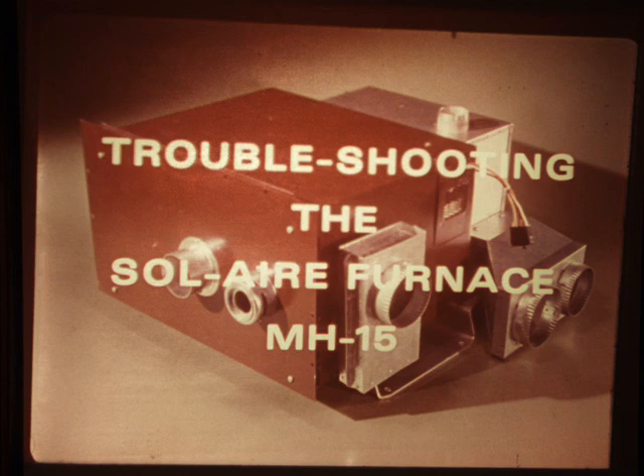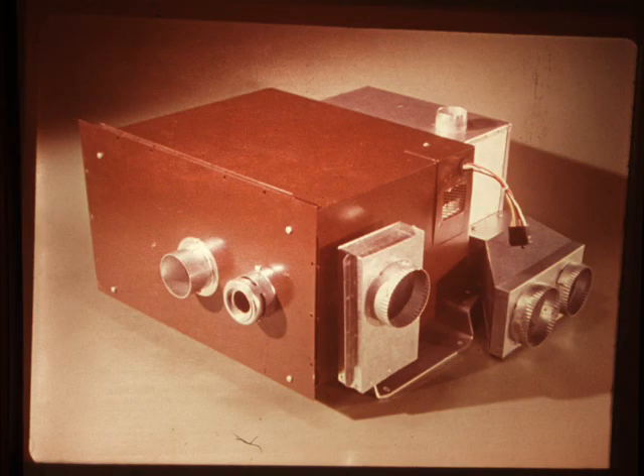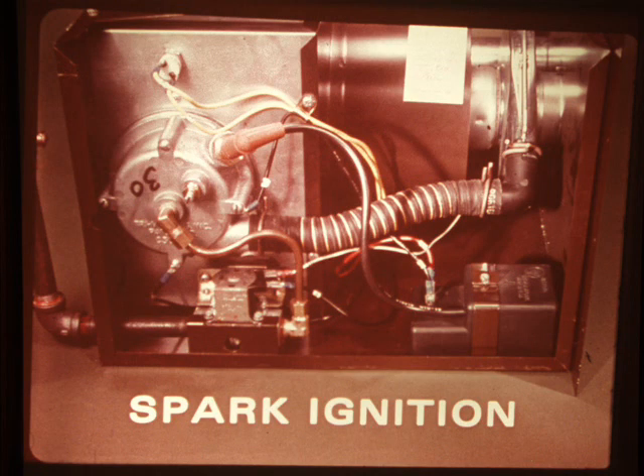Troubleshooting the Solaire furnace. The Solaire furnace is new on 1975 GMC Motorhomes. It is considerably different from the furnaces previously used because it uses spark ignition rather than a pilot light. So its control system is all new.